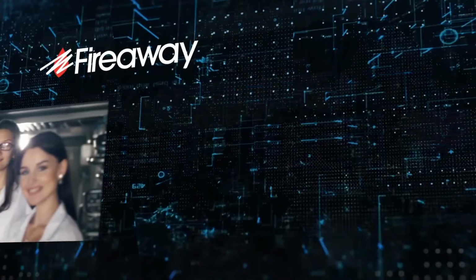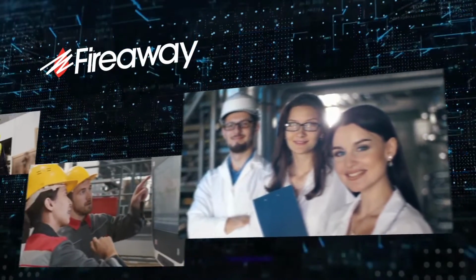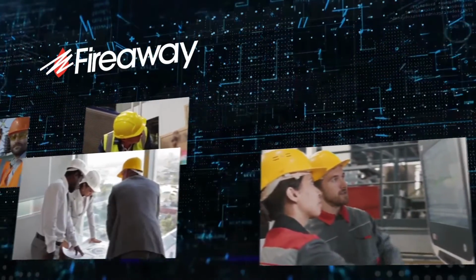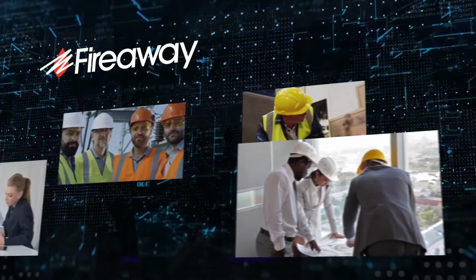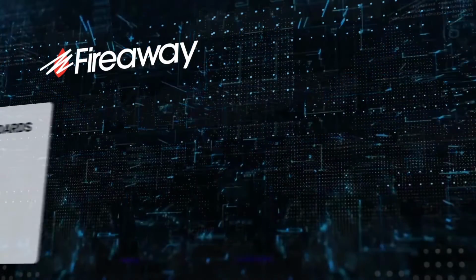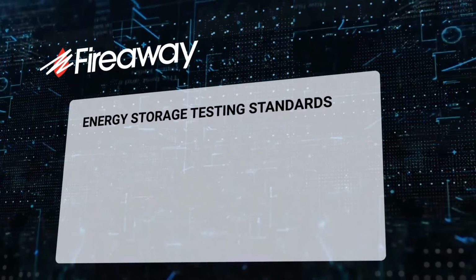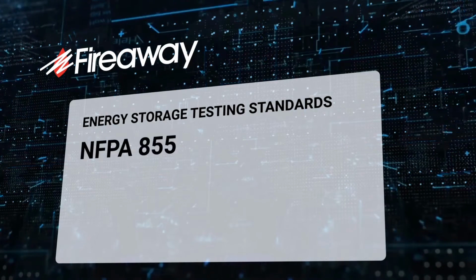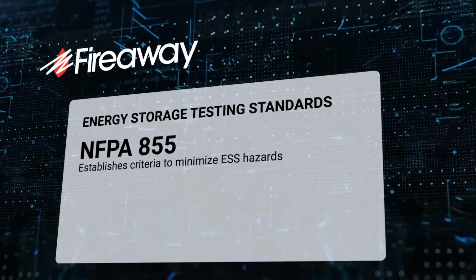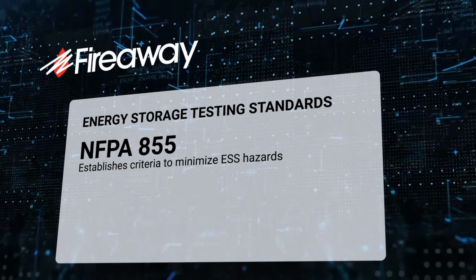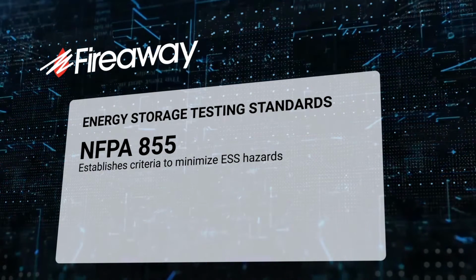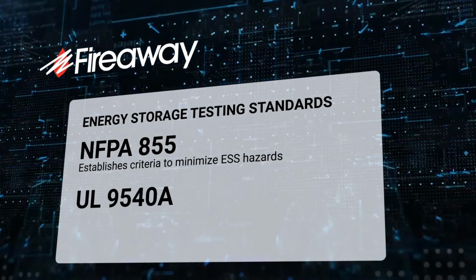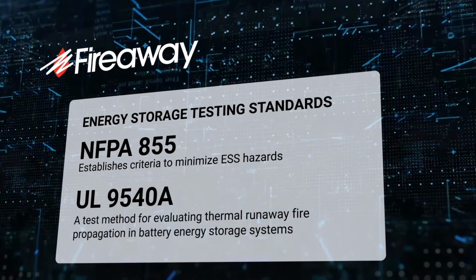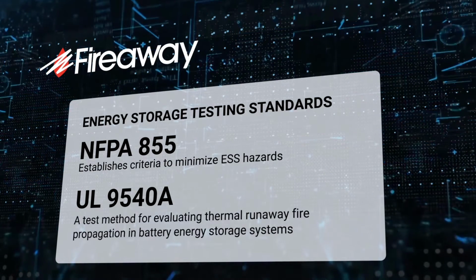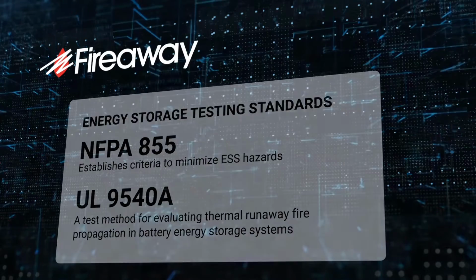At FireAway, product testing is a top priority. All testing meets and exceeds industry standards. There are two standards that are relevant to energy storage applications in testing. NFPA 855, which establishes criteria for minimizing hazards associated with ESS. UL 9540A, a test method for evaluating thermal runaway fire propagation in battery energy storage systems.